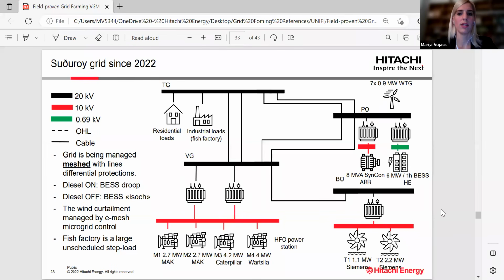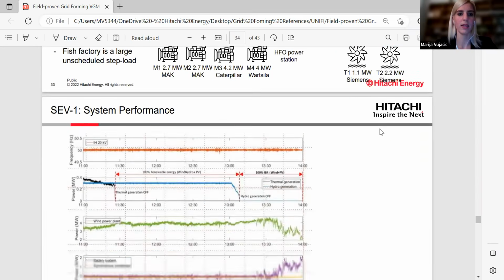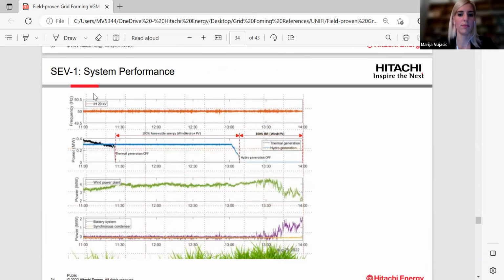So as you can see here, both the synchronous condenser and the battery energy storage system were added to this feeder. Sorry, maybe the quality of the figure is not the best, but we have only a limited number of recordings, as this system has been in operation for only a couple of months. But the customer is quite happy with the frequency being regulated by a battery energy storage system.